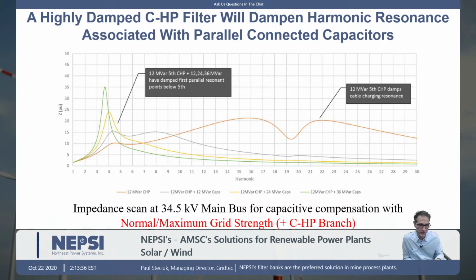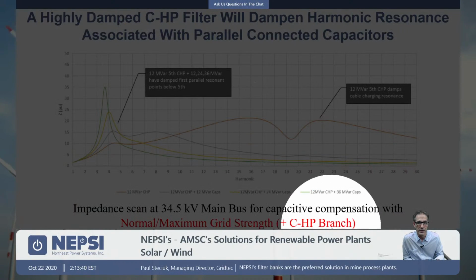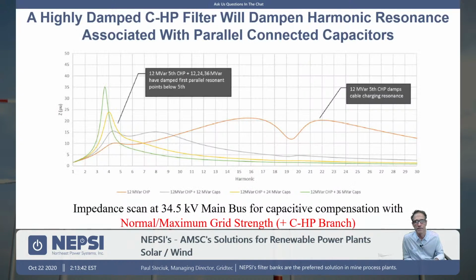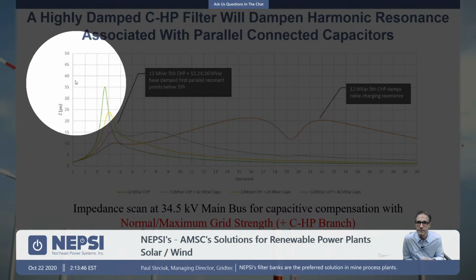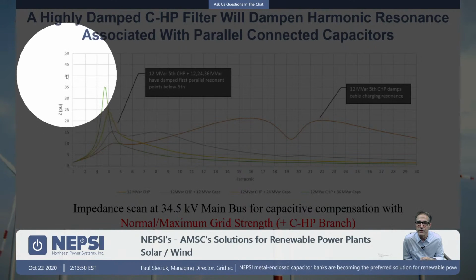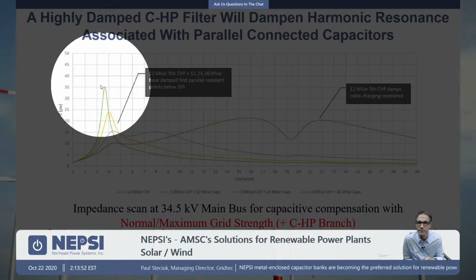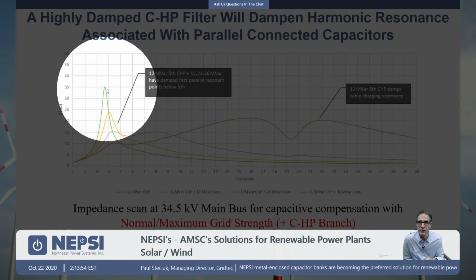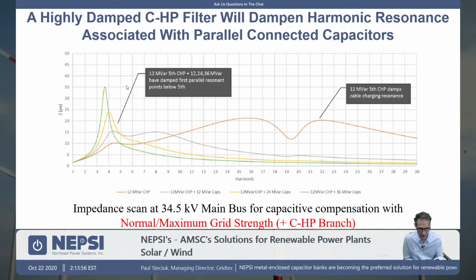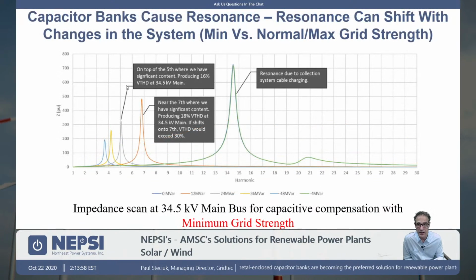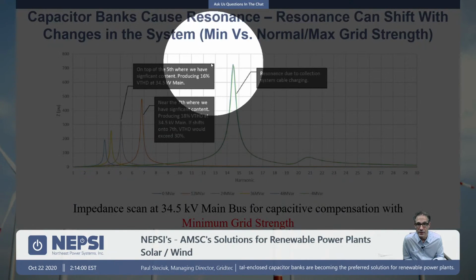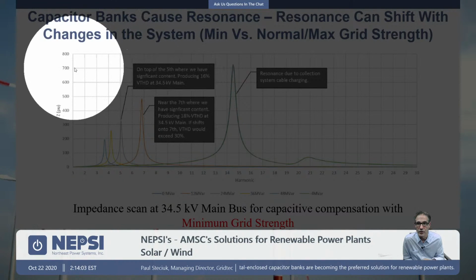Well, one solution to that is to put a C high pass filter in, and that's what we did with this customer. We added this C high pass harmonic filter branch at stage 1. And what we did, and it's kind of interesting to note here, is you can look at the axes of the curve here. This is the impedance curve, and we have Z per unit here. You can see that the peak, the worst resonant condition, peaks out at about 35 per unit. If I go back to the previous slide, you can see that here we have 700 per unit.